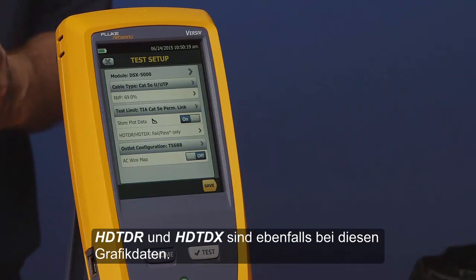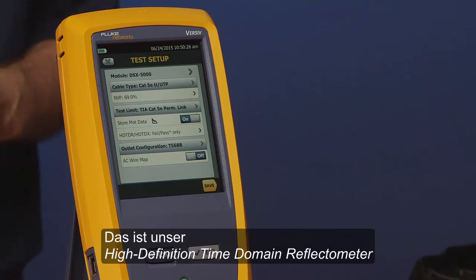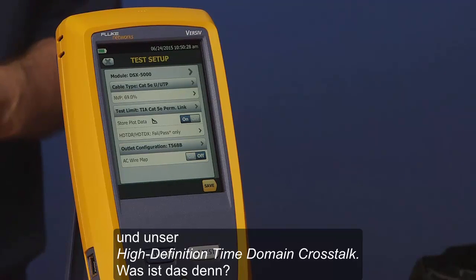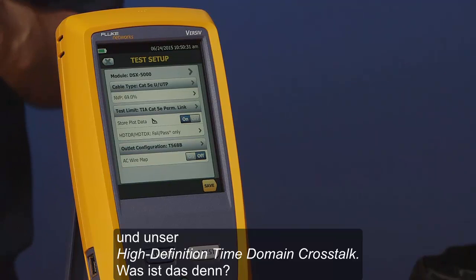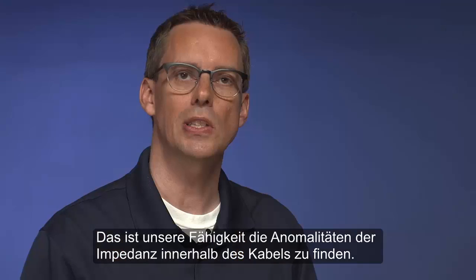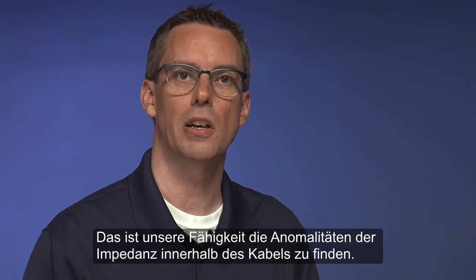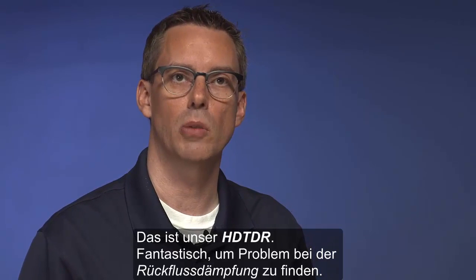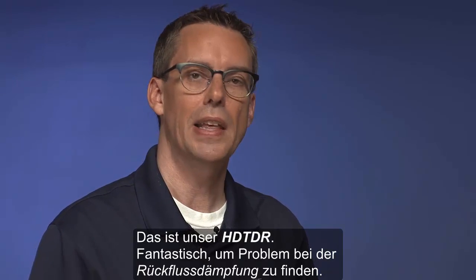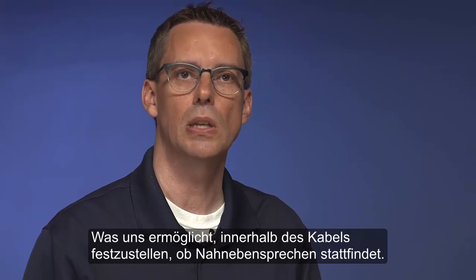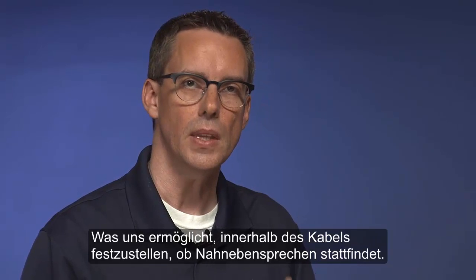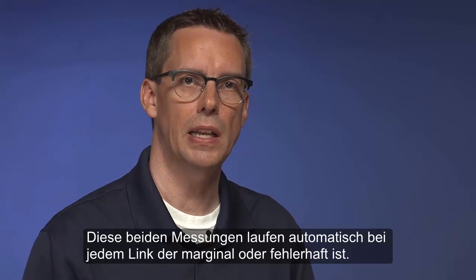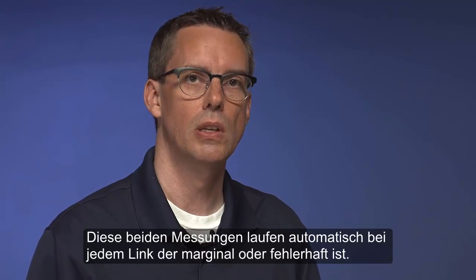Below store plot data is HDTDR and HDTDX. That's our high definition time domain reflectometer and our high definition time domain crosstalk. That's quite a mouthful. That's our ability to look down the cable and see where the impedance anomalies are. That's our HDTDR. Fantastic for troubleshooting return loss issues. And then our HDTDX is crosstalk. That allows us to look down the cable and see where the crosstalk is occurring. These two tests will run automatically on any links that are marginal or failing.